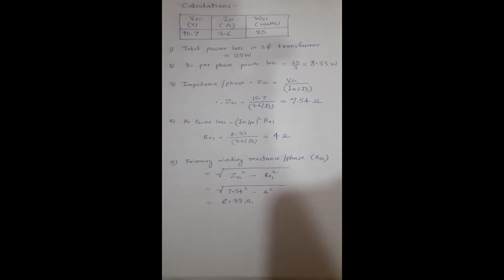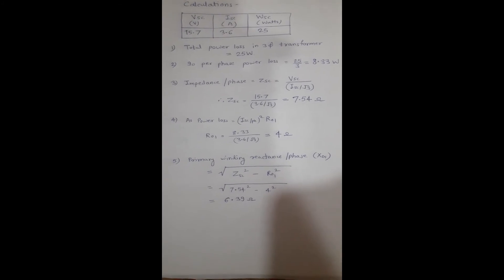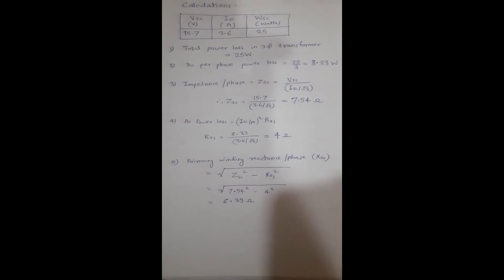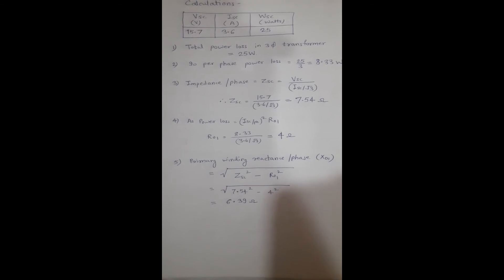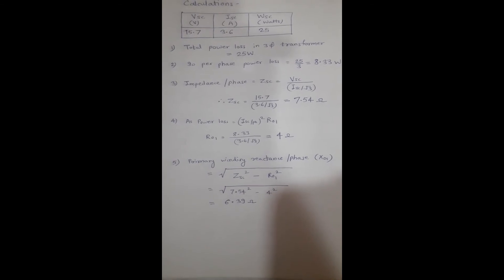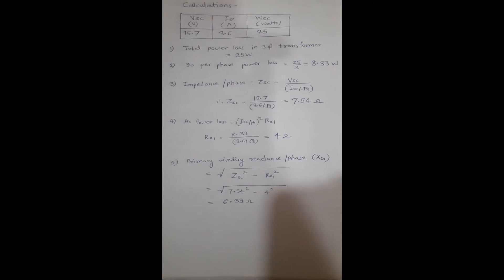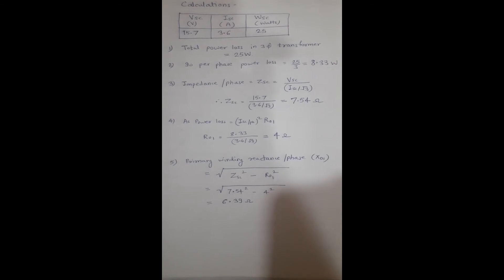The last parameter to calculate is reactance per phase, X01. The formula is X01 = √(Zsc² − R01²). Substituting the values of Zsc = 7.54 ohms and R01 = 4 ohms into this formula, we get the primary winding reactance per phase X01 = 6.39 ohms.